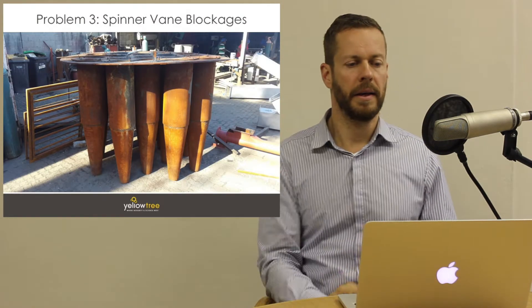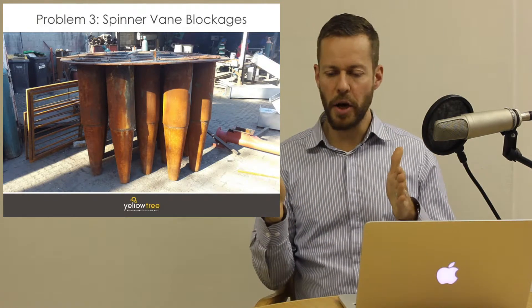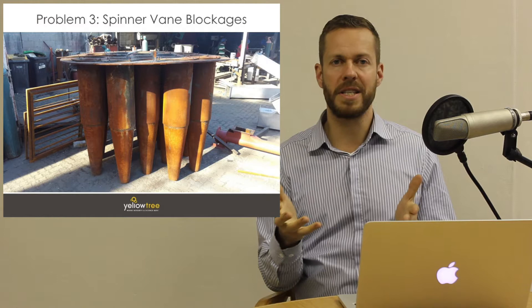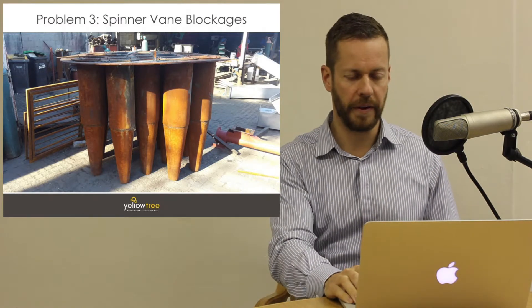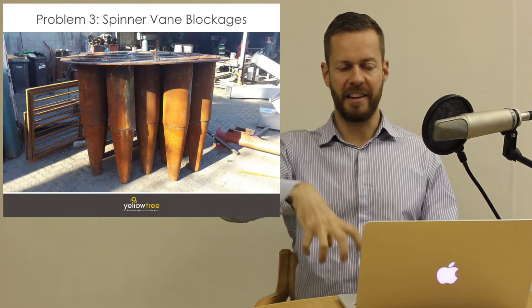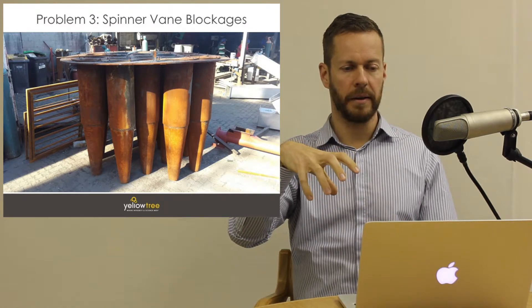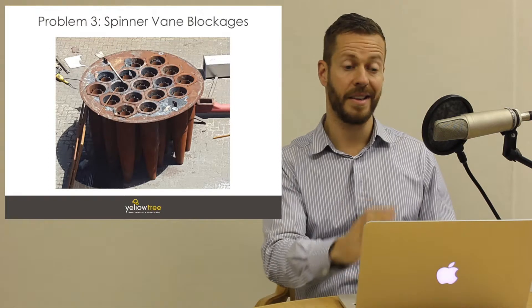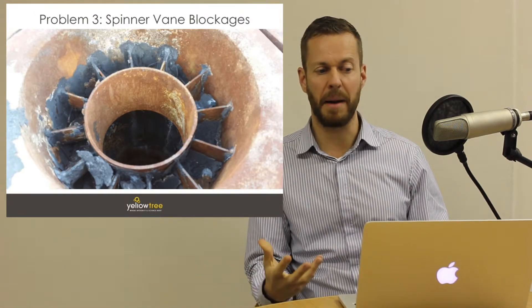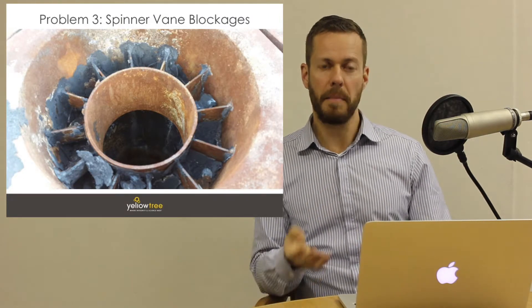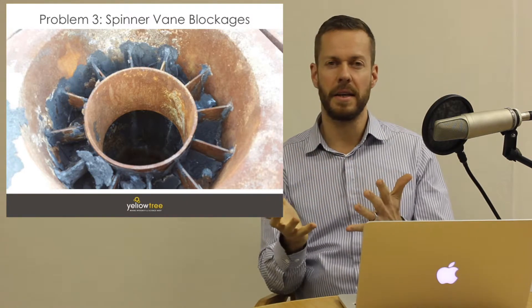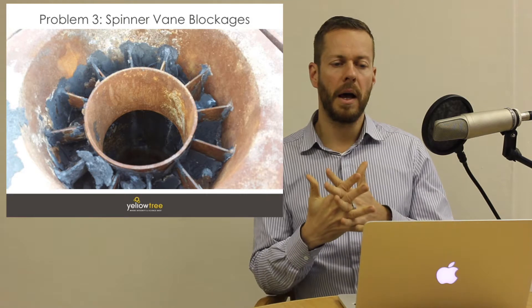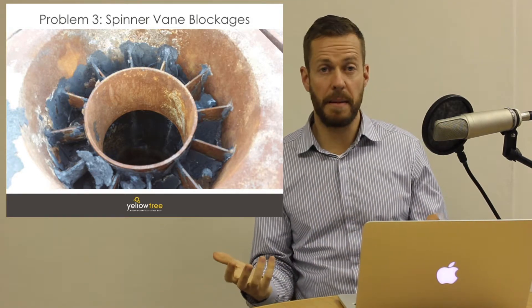Problem number three is blocked spinner vanes. Gas flowing into each cyclone must pass through spinner vanes that start the spiralling motion — but what happens if those spinner vanes get blocked? This photograph shows individual cyclones lifted with a crane out of the body of the multicyclone. Looking at the tops, we can see the spinner vanes, and on this particular multicyclone they have become blocked with particulate matter. This typically happens when the manufacturer spaces the spinner vanes very close together, which is common in modern multicyclones, meaning they need to be cleaned very often.